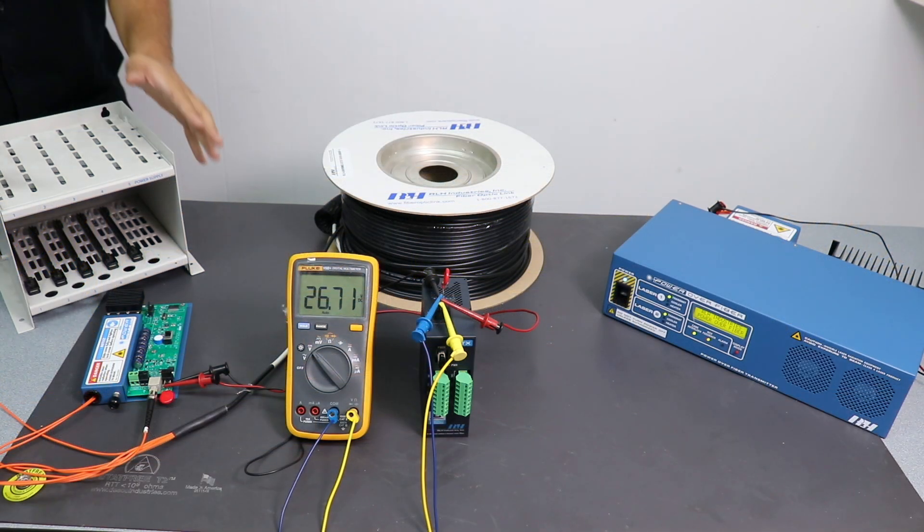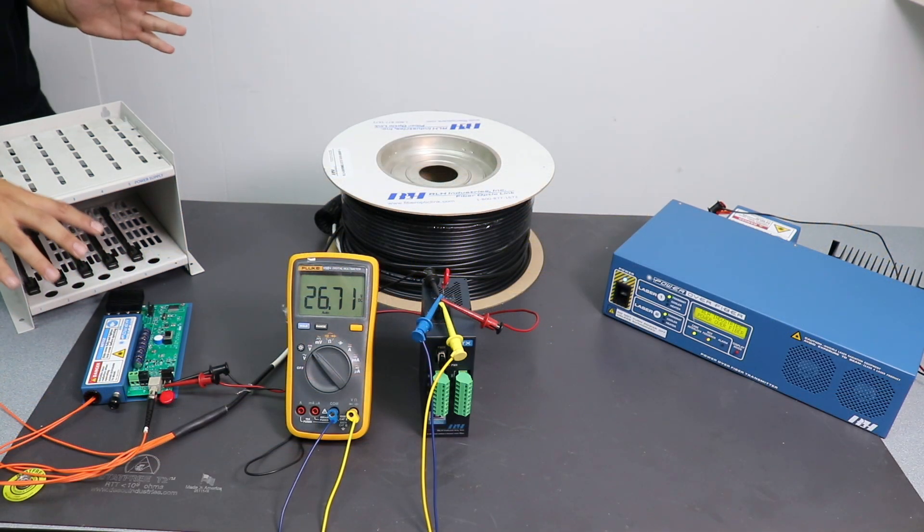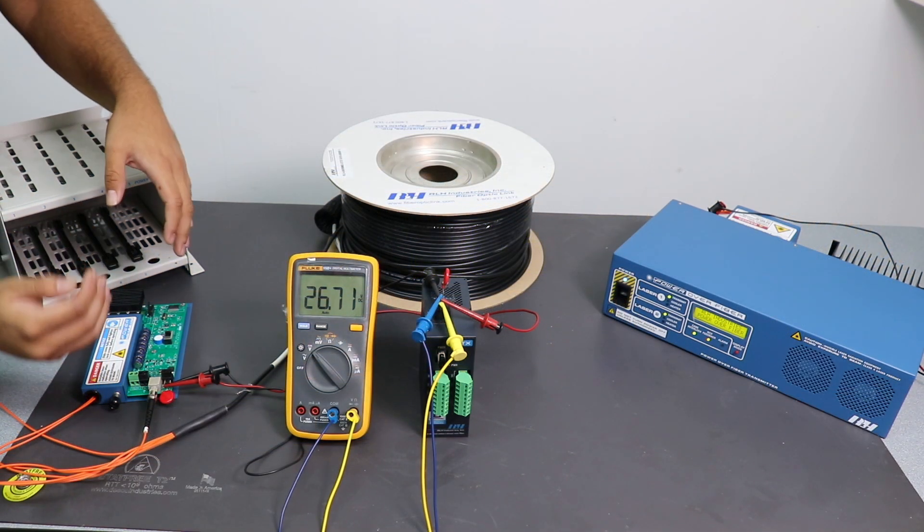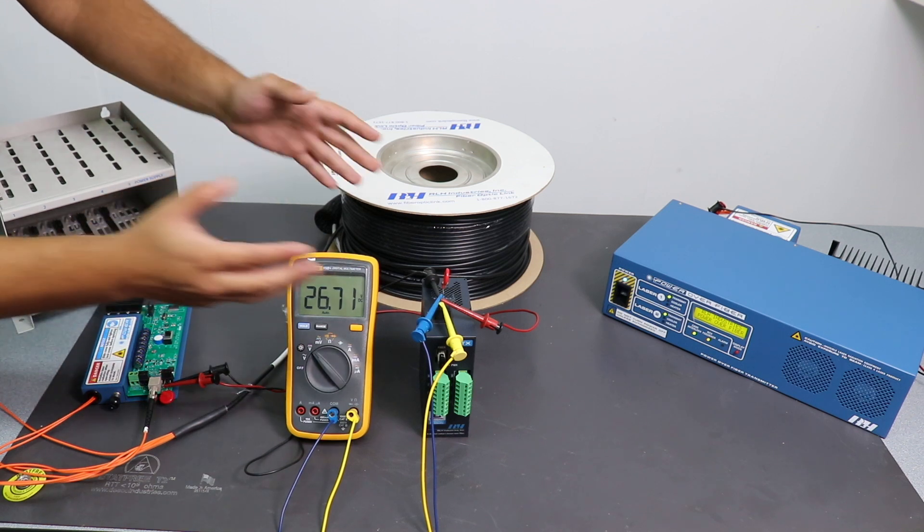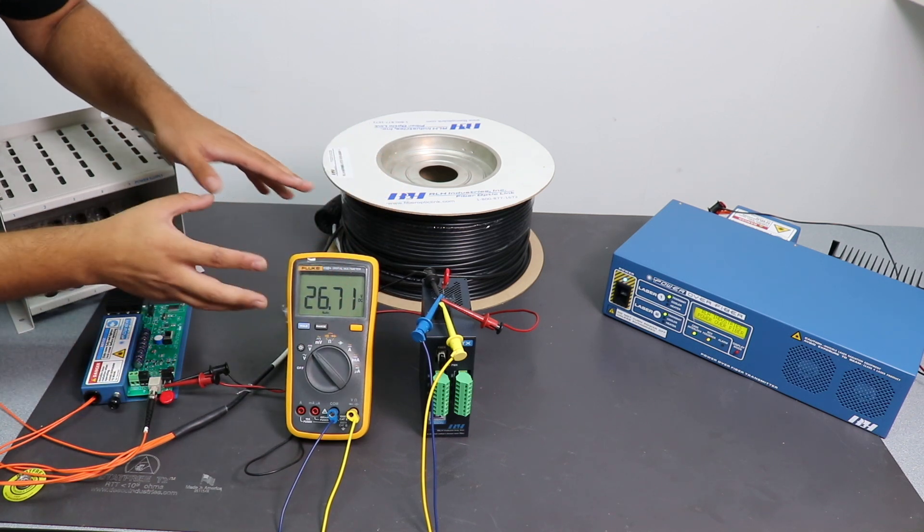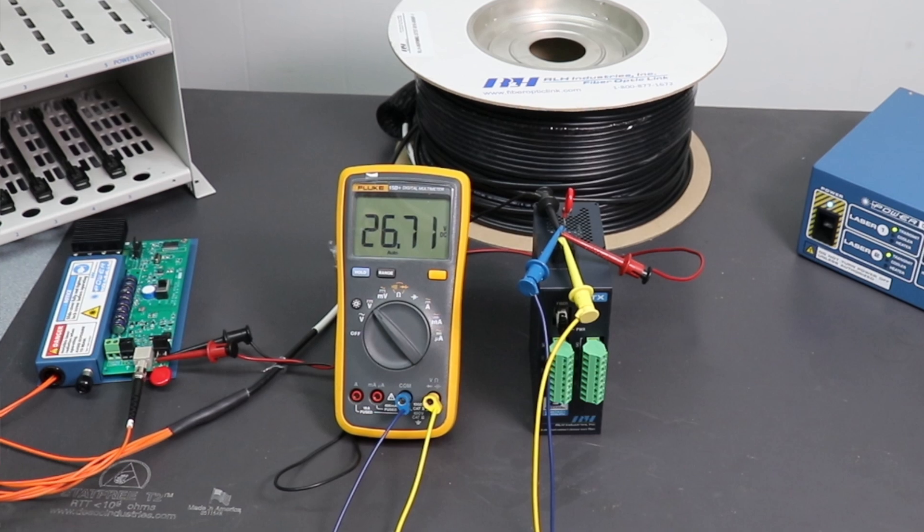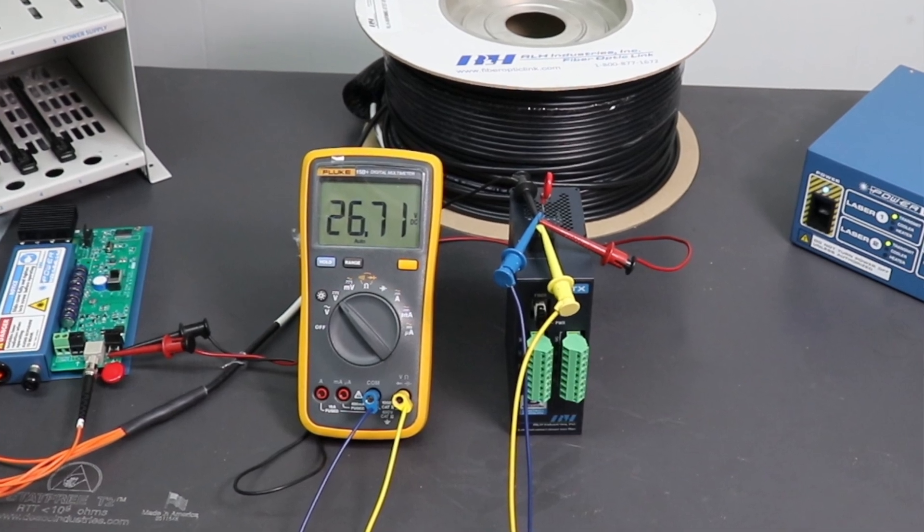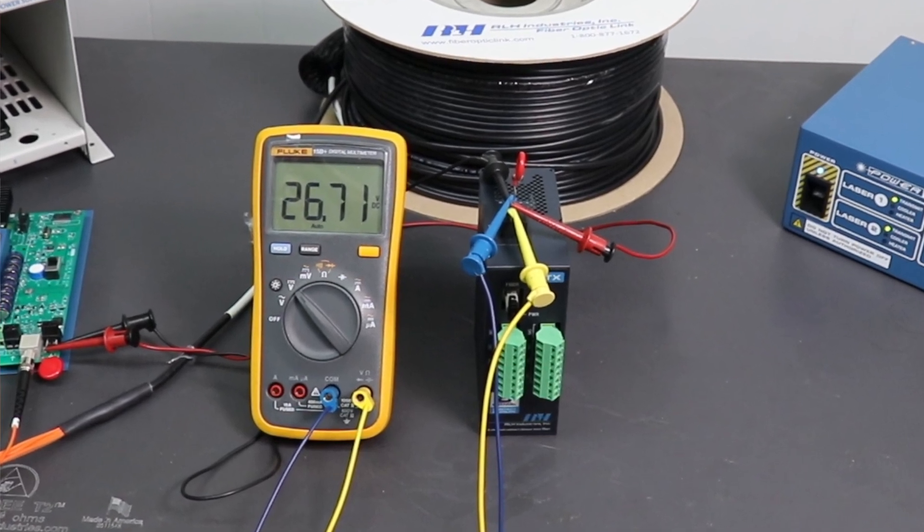Coming at this side now, we have your RX card over here. Now, I connected this RX card to our own contact closure system over here. And also, using a multimeter, I'm showing what voltage you're going to see on this side. So I'm seeing 26.71 volts on this side.